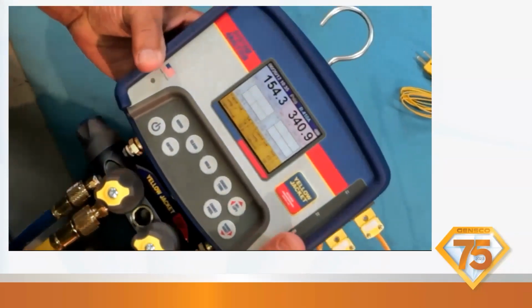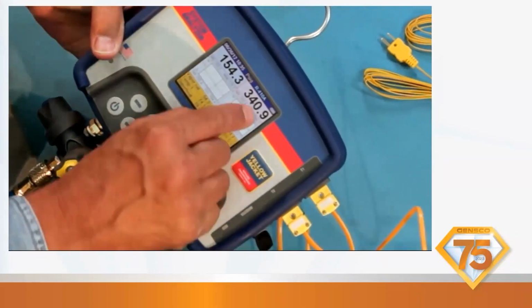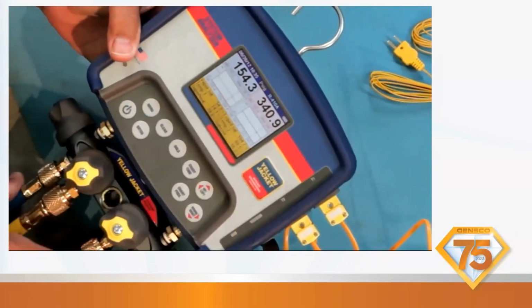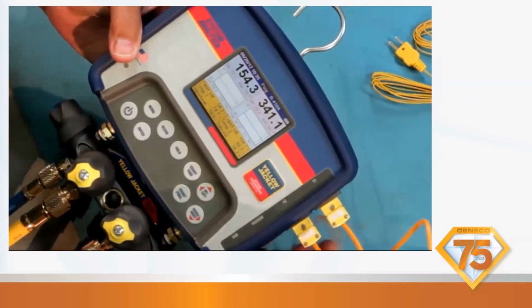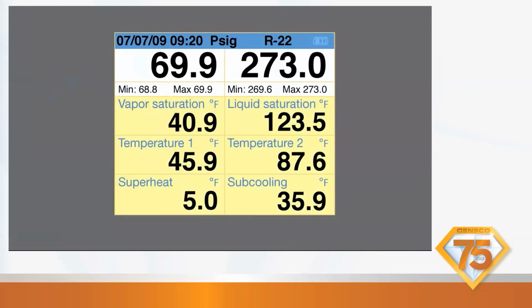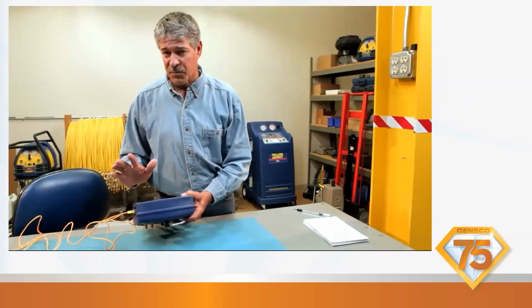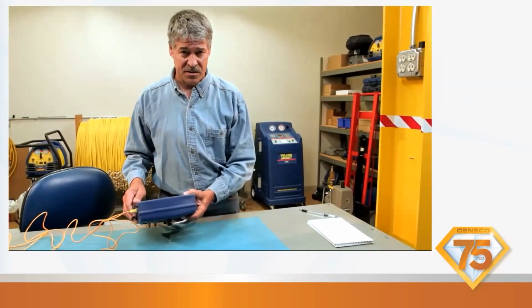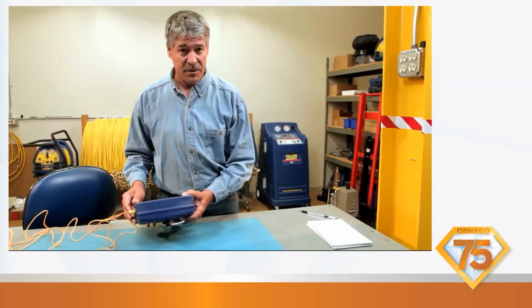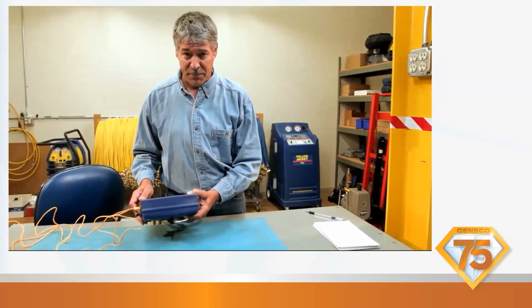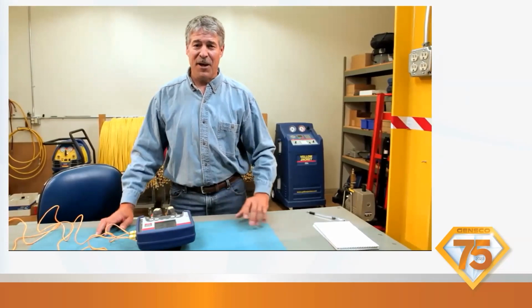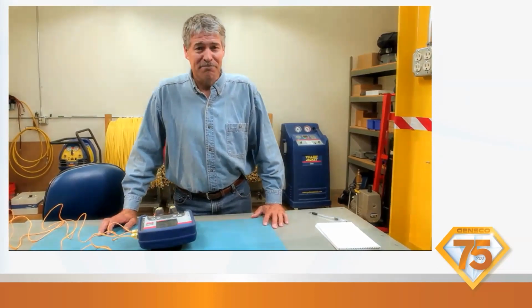If you're using a refrigeration system analyzer, simply select the appropriate refrigerant and connect the hoses and thermocouples to the system for an immediate reading. The unit will automatically determine saturation temperatures and calculate the superheat and subcooling. For the most precise readings, make sure your refrigeration system analyzer has elevation compensation settings and accurate temperature probes. That's it for now. Until next time, thanks for watching.